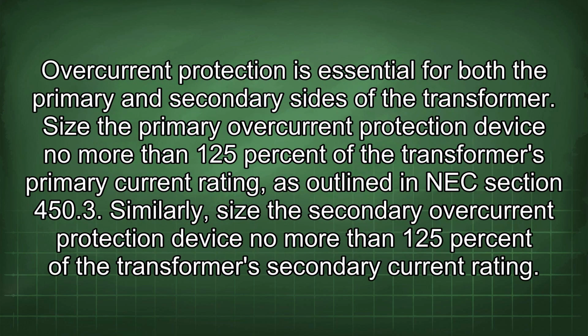Overcurrent protection is essential for both the primary and secondary sides of the transformer. Size the primary overcurrent protection device no more than 125% of the transformer's primary current rating, as outlined in NEC Section 450.3. Similarly, size the secondary overcurrent protection device no more than 125% of the transformer's secondary current rating.